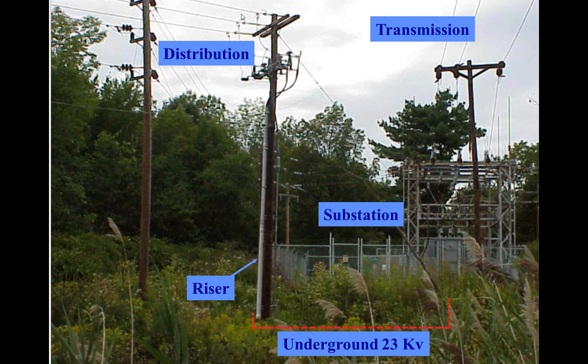There's what we call primary, overhead primary. That's three phase. Each wire is referred to as a phase, and that is what we call a three-phase primary distribution system right there. The other configuration, if you look on top of the pole and you see less than three wires, that's a single phase. But one of the wires would be the neutral that's going back to ground. The other one will be the hot primary distribution voltage. So if it's on top of the pole, those wires are primary. You treat them all with respect, right?